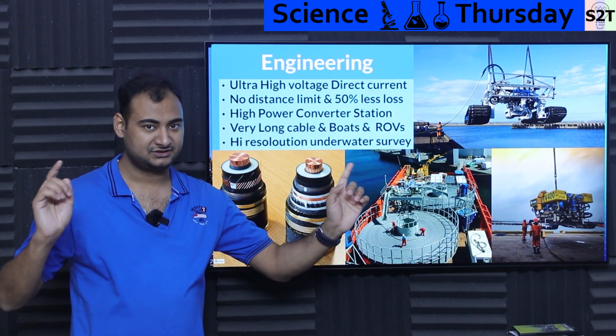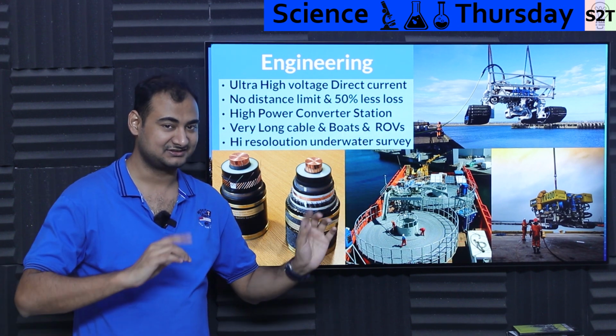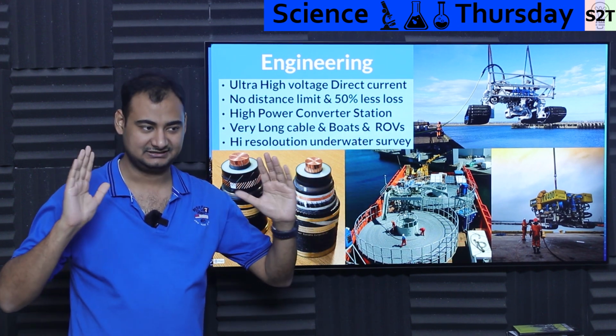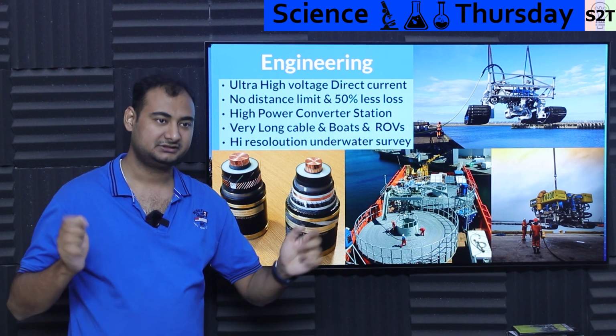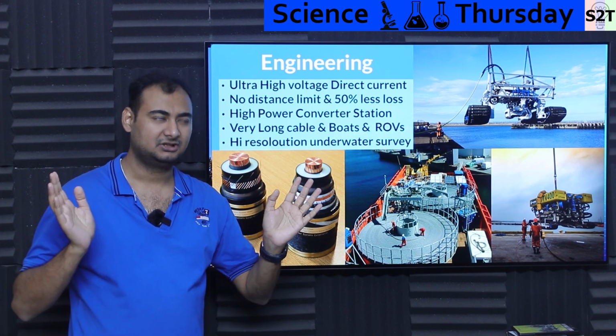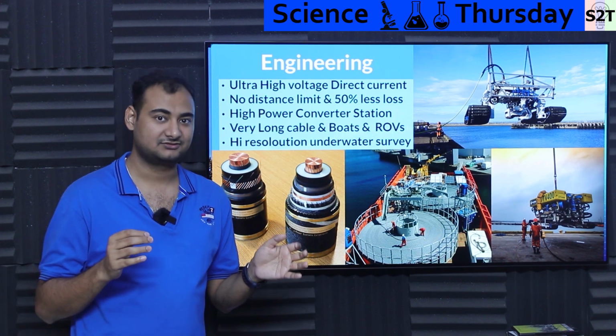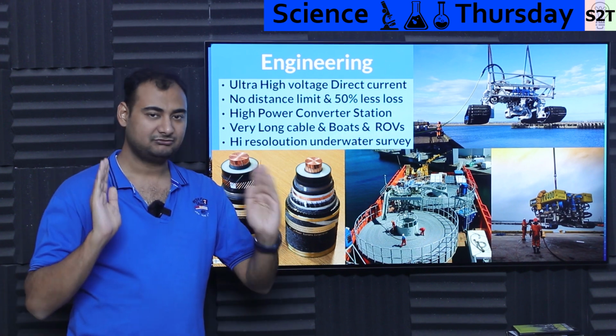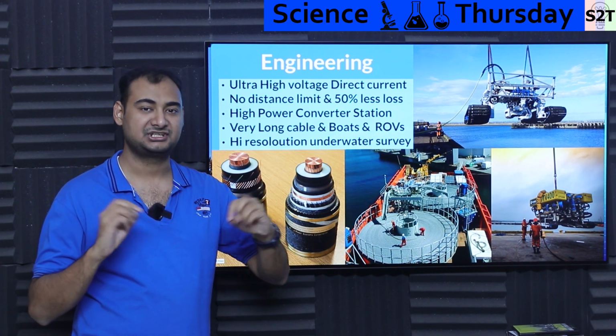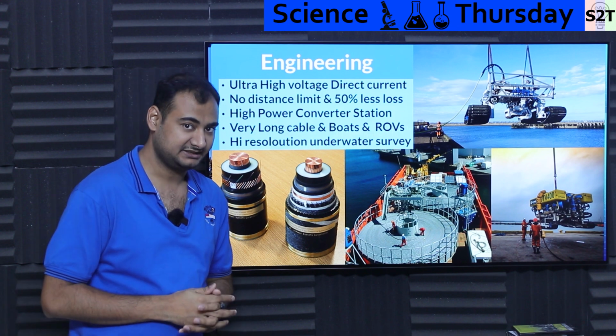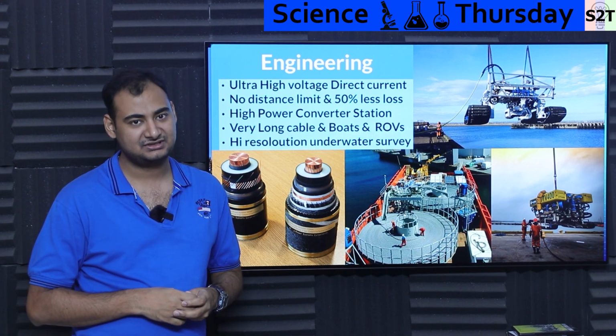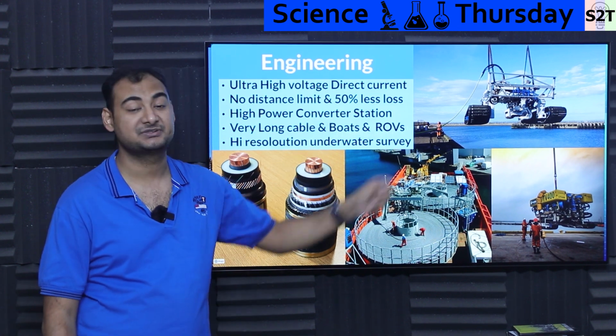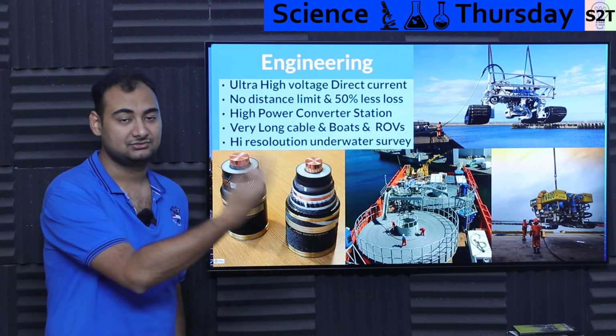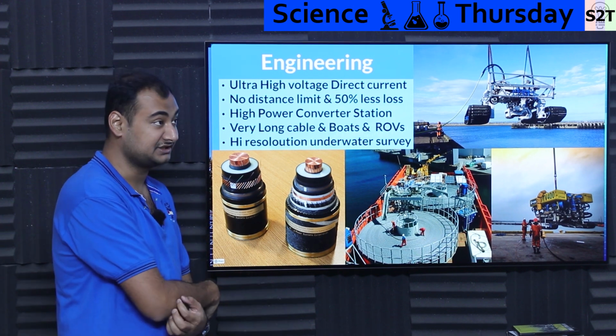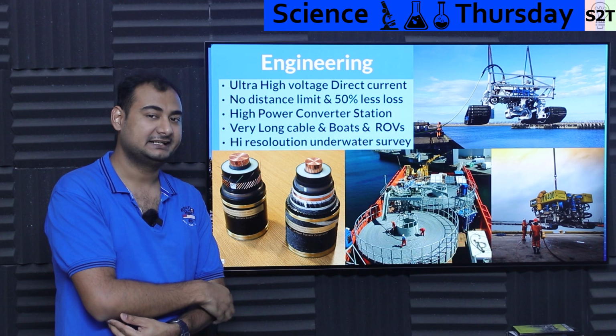If you have 1000 kilometers, be mindful of capacity - I'm not talking about capacitance loss. If you have 1000 kilometers, how much energy just poofs away? Well, it's not calculated for 1000 kilometers, generally it's calculated per 100. So for that 1 unit of 100 kilometers, how much energy is lost? That's 6% in an AC grid. How much is lost using DC? It's 3%. That's why people say 50% less energy loss. So compared to 6% loss, you only lose 3%. And when we're talking about gigawatts, that loss really matters.